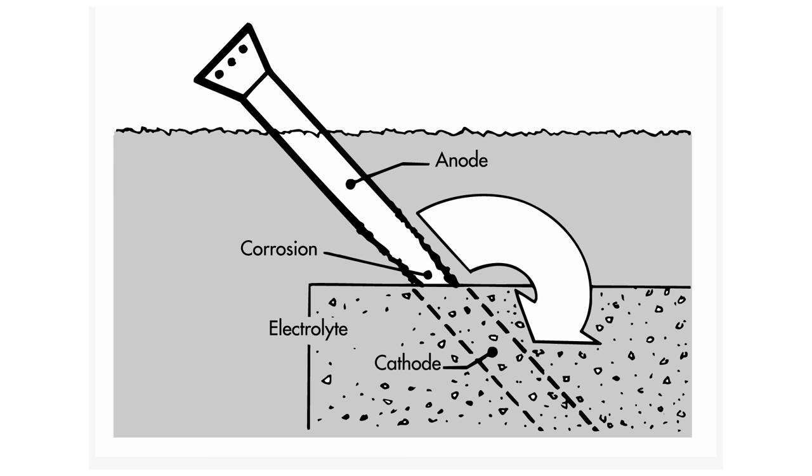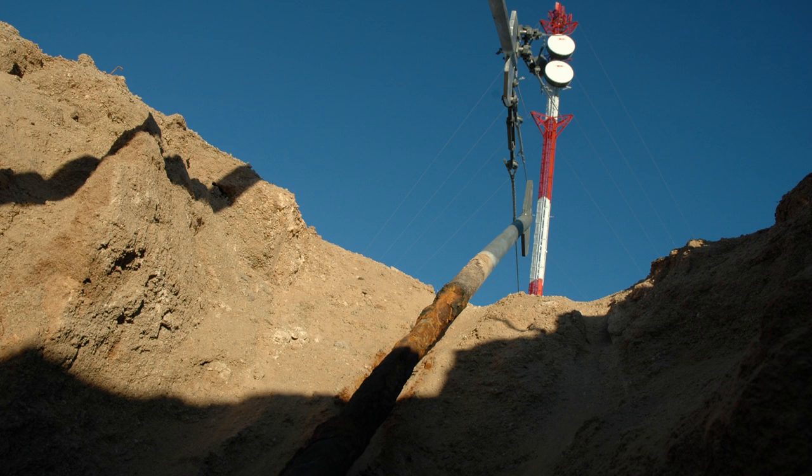In the example of a guyed tower anchor, the soil is the electrolyte and the portion of the anchor shaft exposed to the soil is the anode. Soil resistivity varies drastically throughout the globe and can even change down to a matter of inches. The soil resistivity can be measured on site to get a better idea of soil conditions.